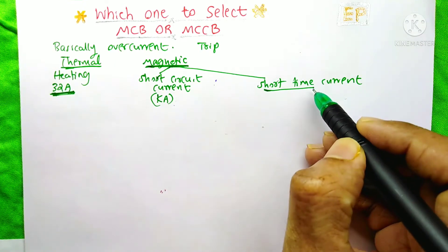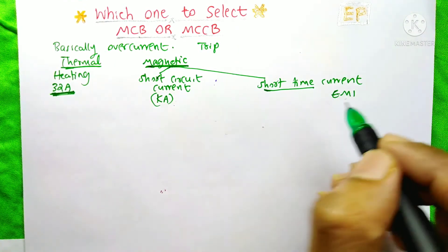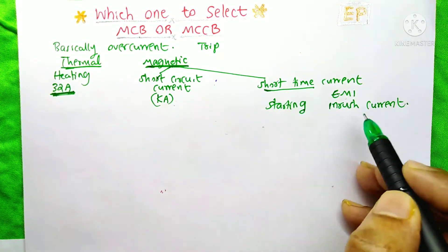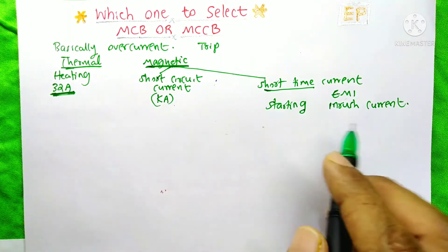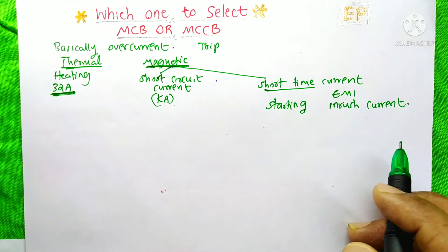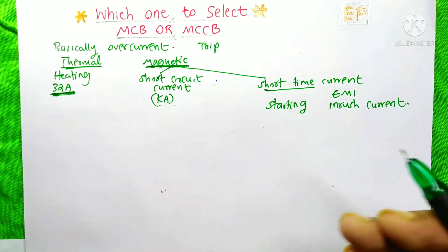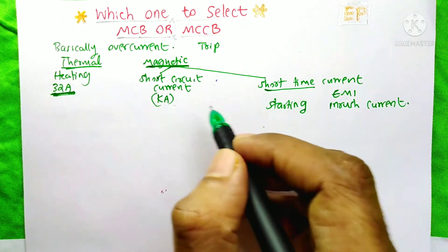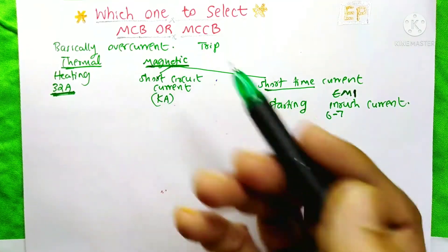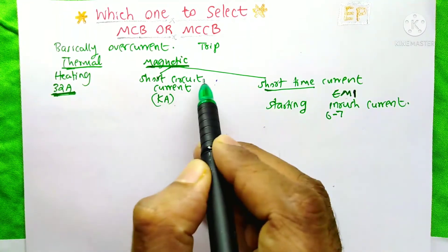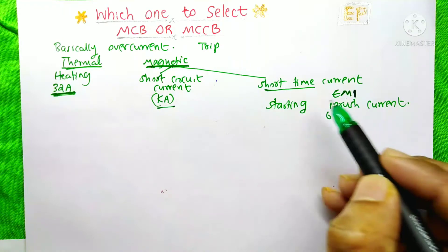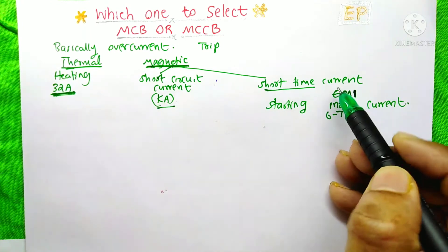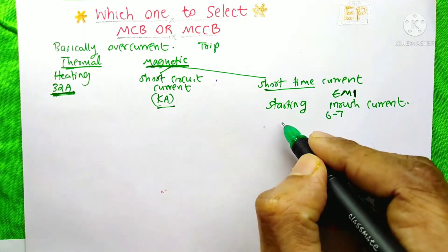Whenever any appliance working under the principle of electromagnetic induction starts up, it produces a high inrush current in the circuit. The MCB or MCCB should not trip because of this inrush current, as it is a normal occurrence and lasts only a few seconds. But sometimes this inrush current is more than expected, and then we need to trip the circuit. In both MCB and MCCB, the short circuit current setting is automatic, but the short time current can be adjusted only in the MCCB. In MCB, short time current behavior depends on the B, C, D curves.